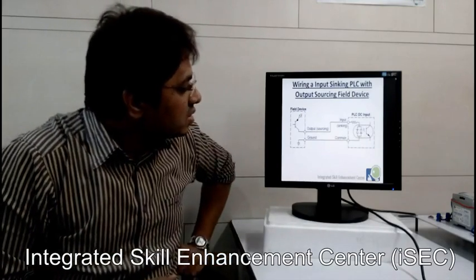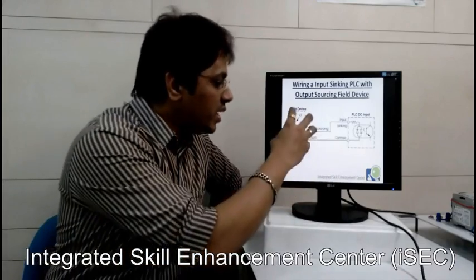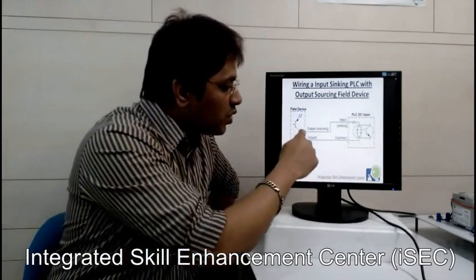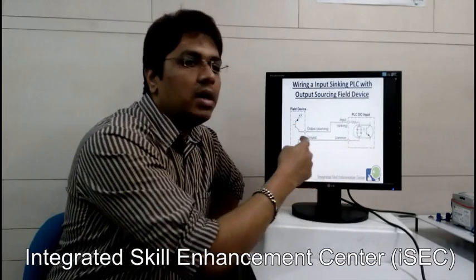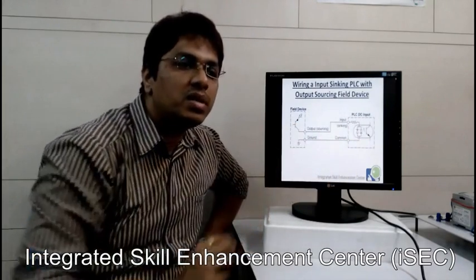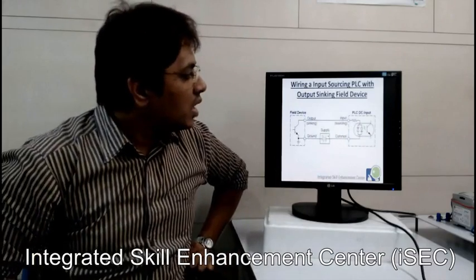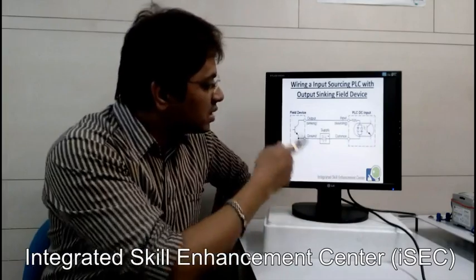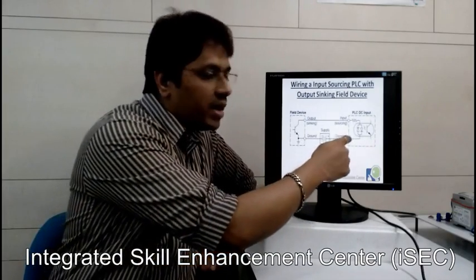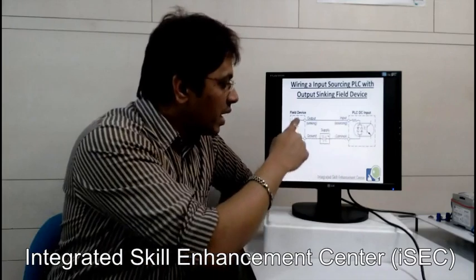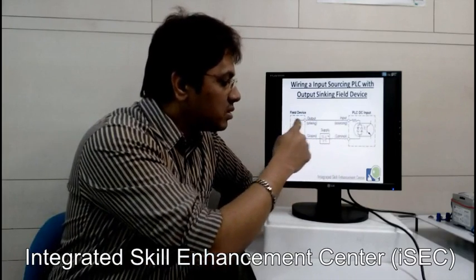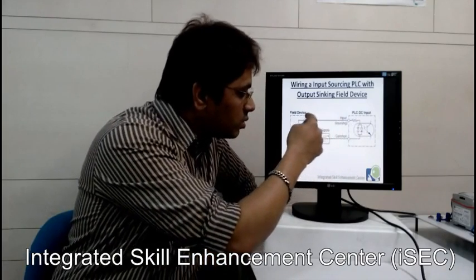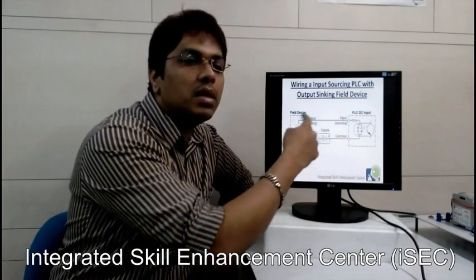Wiring a sinking input PLC with a sourcing output field device: the field device is sourcing and PLC input is sinking. Since the field device provides VCC, you provide common ground to the PLC. When there is a sourcing input PLC and the field device is sinking, you provide common VCC to the PLC.